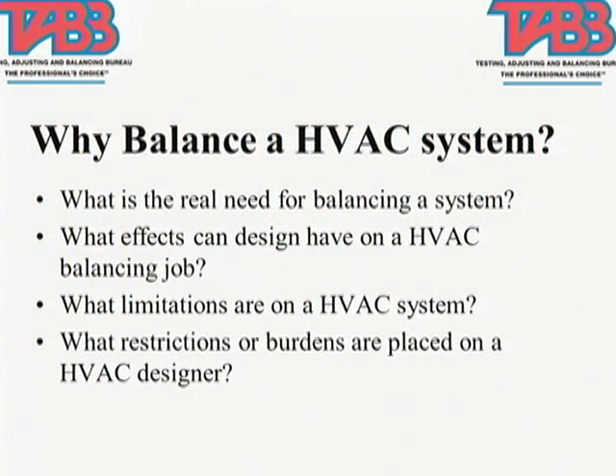Then I like to touch base and say what else happens is you say, well, we need to get a boiler in the area of this hotel that has 98,000 BTUs of heat. And we go to the catalog, and as engineers, you don't go to the catalog and say, oh, I'm going to order one that's 98,000 BTUs. You look at it and you say, there's one that's 75,000 BTUs and one that's 125,000 BTUs, and which one am I going to put in? Typically they oversize it so that we're not stuck on our design days and it wouldn't be meeting the need. So the first thing we did was we put in the wrong size duct, the wrong size pipe, and now we're putting in the wrong size unit.